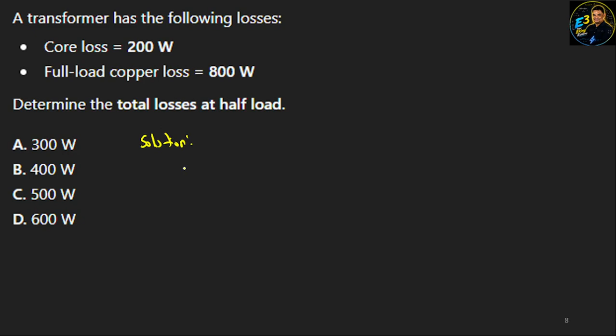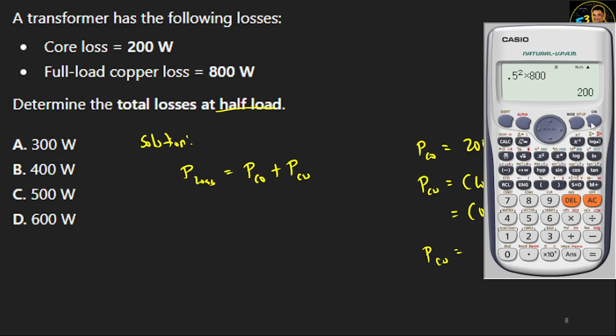P loss natin, this is equal to the sum ng dalawa nating losses: the core loss, which is PCO, at yung isa naman is the copper loss. From the given, our core loss is constant, which is 200 watts. Habang yung ating copper loss naman will depend on the load, so this will be load squared times the full load copper loss. Yung hinahanap sa problem is half load, so that is 0.5 squared, yung full load copper loss natin is 800 watts. Substituting our given: 0.5 squared times 800, that is equal to 200. We have 200 watts.